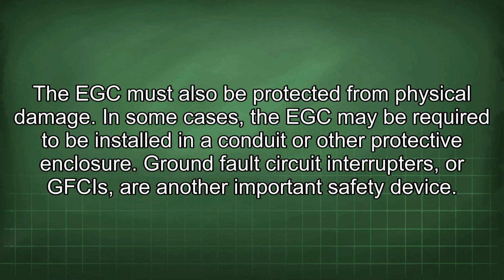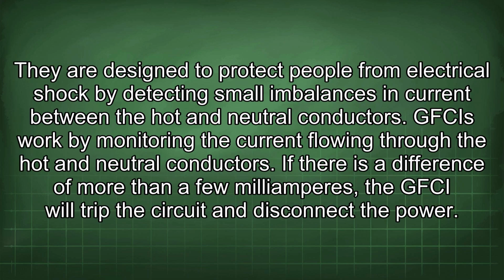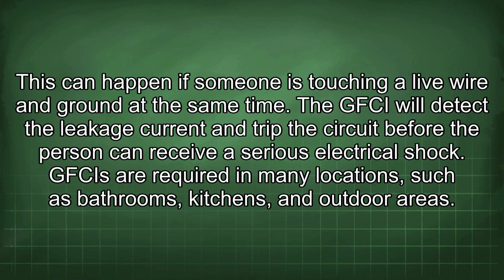Ground fault circuit interrupters, or GFCIs, are another important safety device. They are designed to protect people from electrical shock by detecting small imbalances in current between the hot and neutral conductors. GFCIs work by monitoring the current flowing through the hot and neutral conductors. If there is a difference of more than a few milliamperes, the GFCI will trip the circuit and disconnect the power. This can happen if someone is touching a live wire and ground at the same time. The GFCI will detect the leakage current and trip the circuit before the person can receive a serious electrical shock.